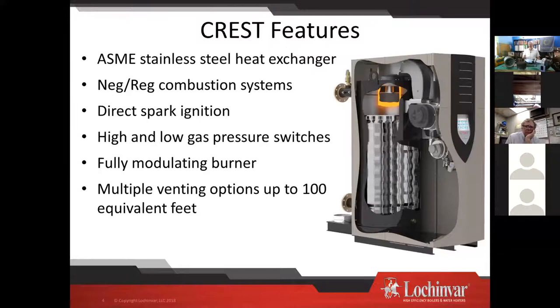It's a very small combustion chamber on the top. The important thing about this picture — and I'm going to hit this several times because it's incredibly important — is the flame on the burner is really tight to that burner. At low fire it's a glow that stays really tight there.